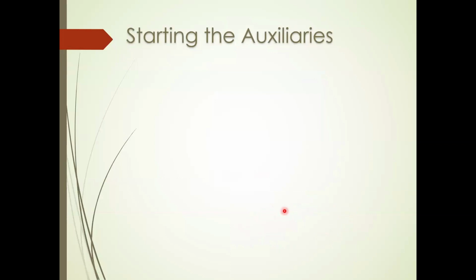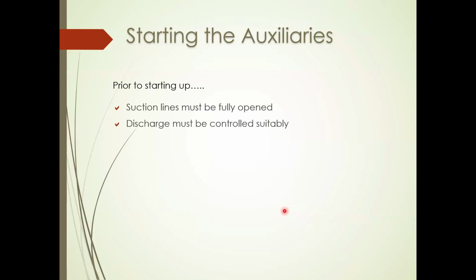Now for all these equipments in each phase, to put them into operation, first we have to achieve their working conditions and do preliminary requirements also. In the case of pumps, of course, you have to arrange a few things prior to the startup. Simply, you have to make sure the suction lines are fully open and suction fluid is available. And of course, sometimes the discharge must be controlled. Sometimes it has to be closed. Sometimes you will control it, open it slightly according to the situation.